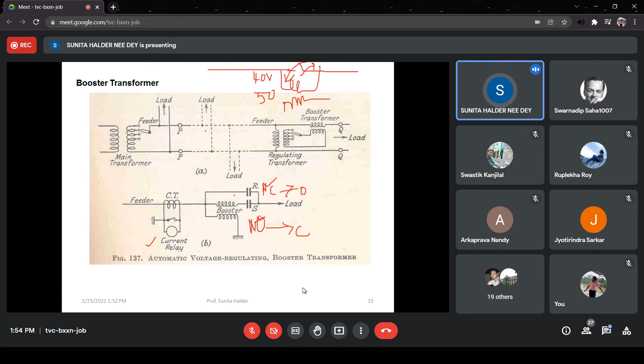Now, from the first picture, I wanted to show that from the main transformer through the transmission line, power is transferred to a particular load. And in between that, there may be tapping or there may be a substation. Now the tapping is there, so through the feeder at the regulating transformer, we can increase the voltage level. But at the same time, when the voltage level is still not at an acceptable value, then we can increase the voltage level using a booster transformer. And a booster transformer can locally increase the voltage level very easily. So that is the use of the booster transformer.